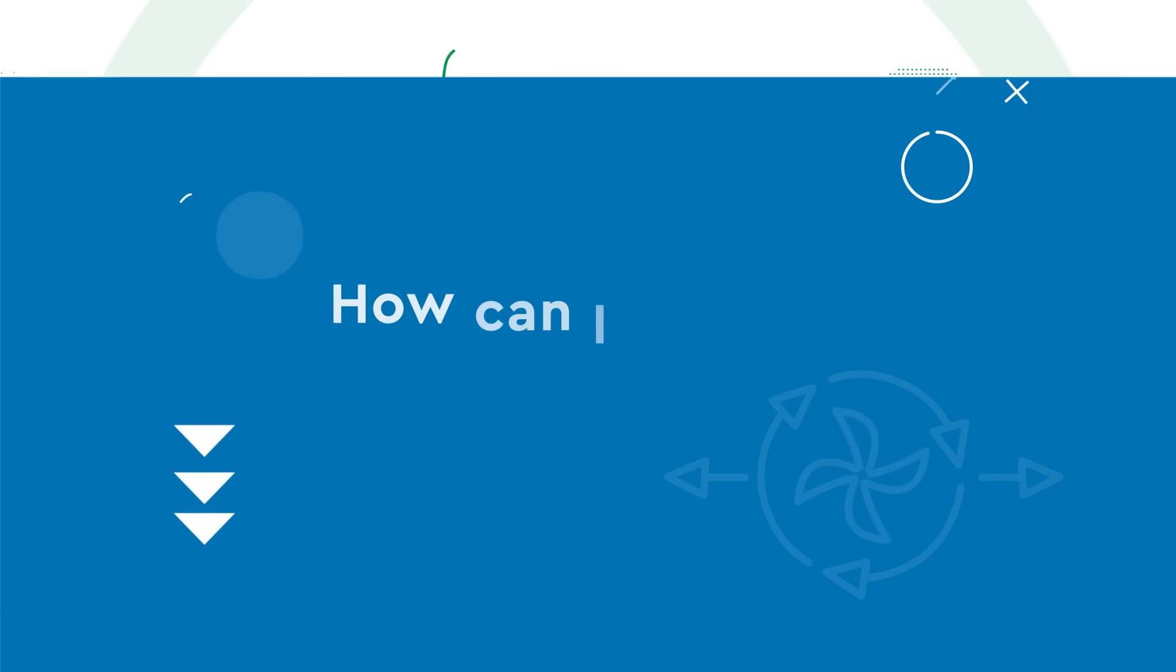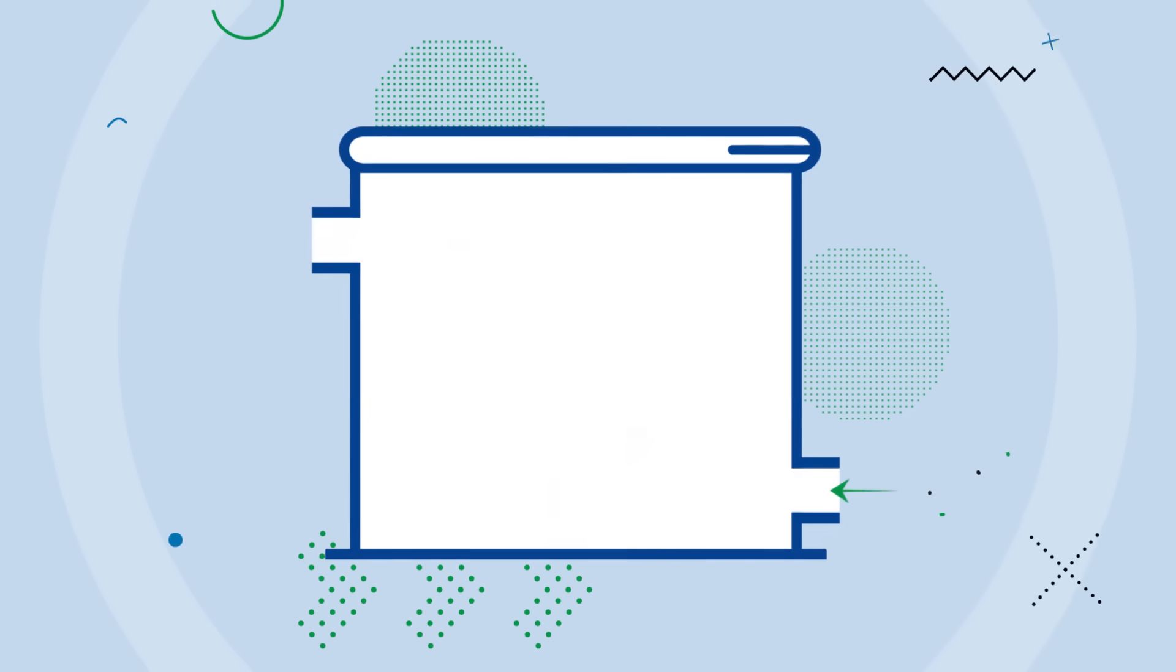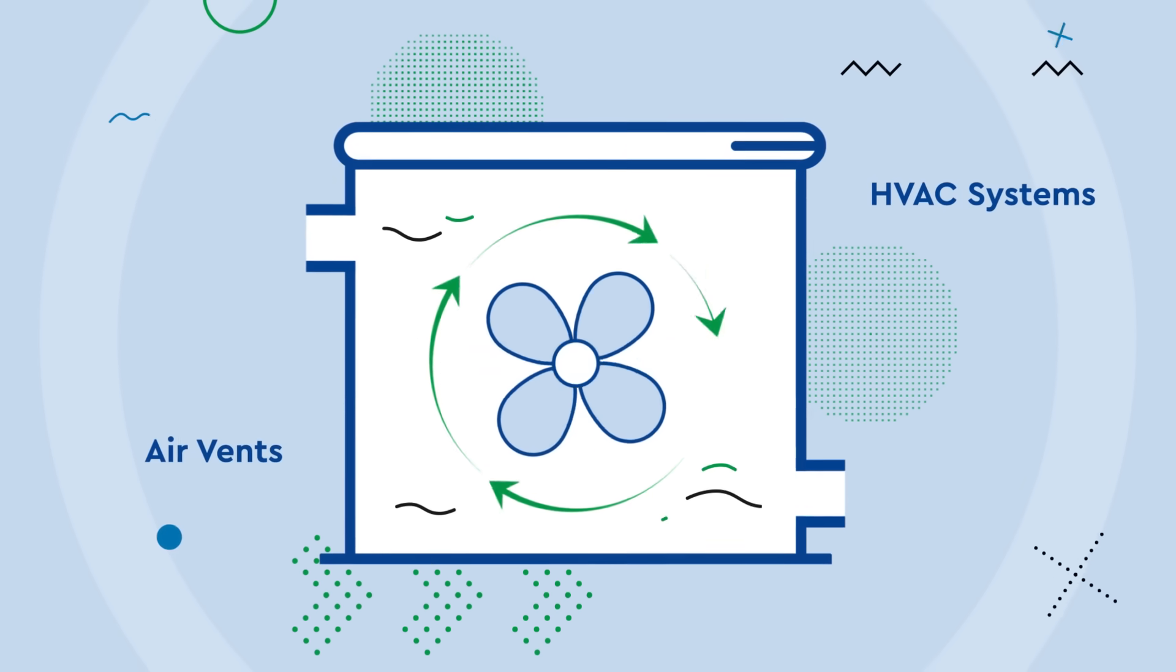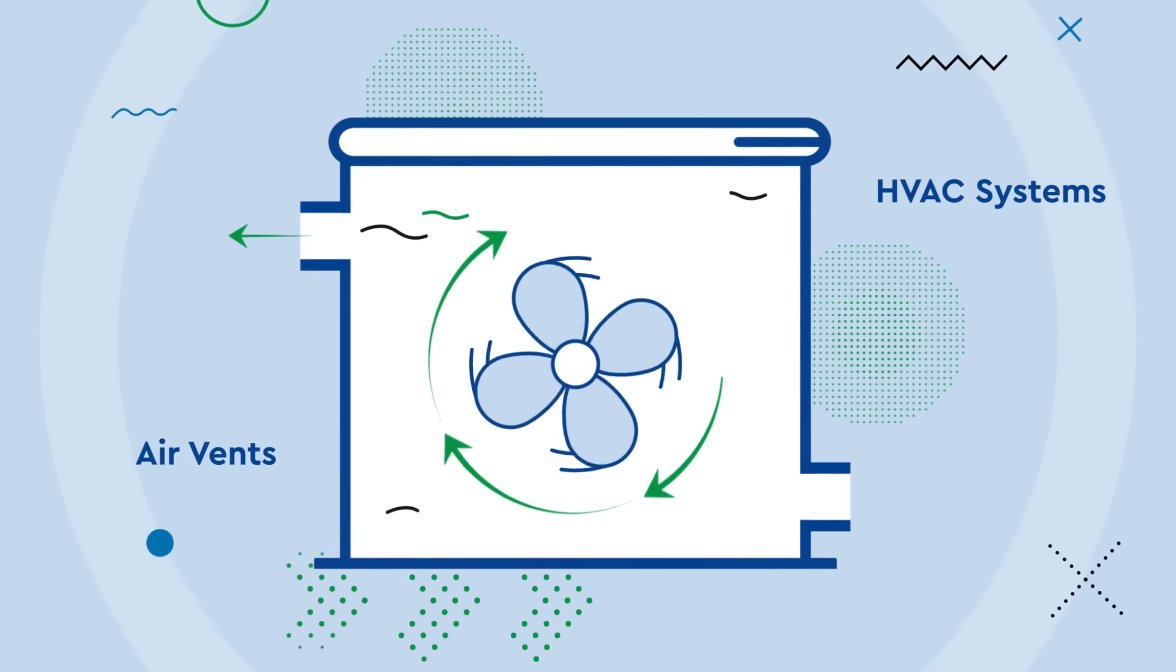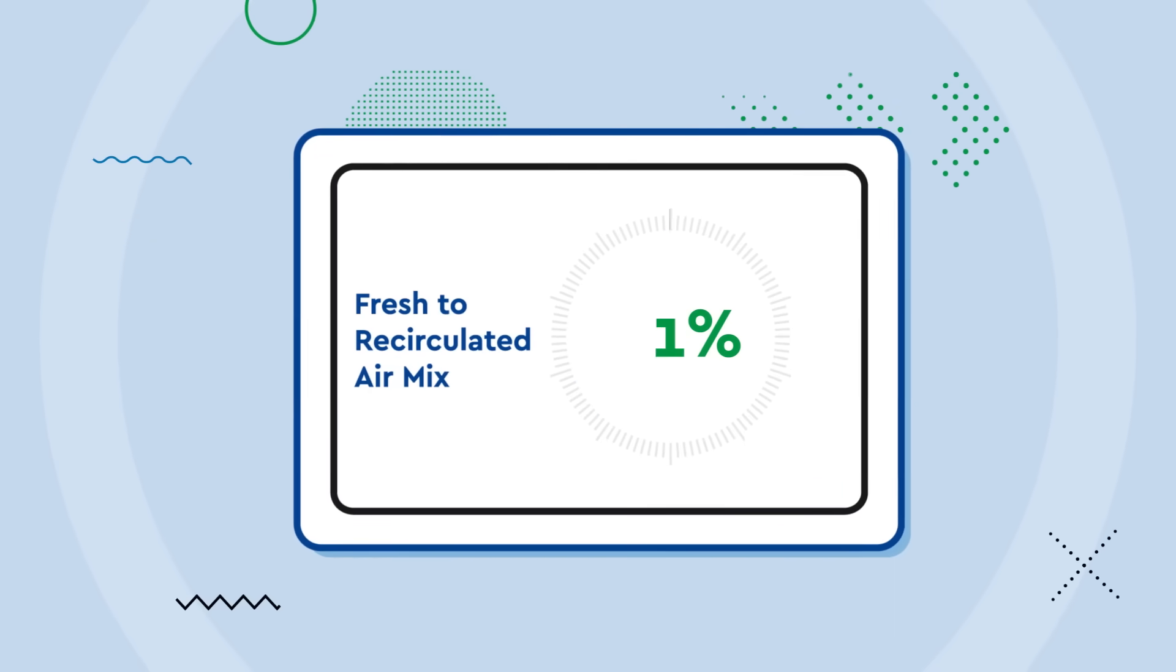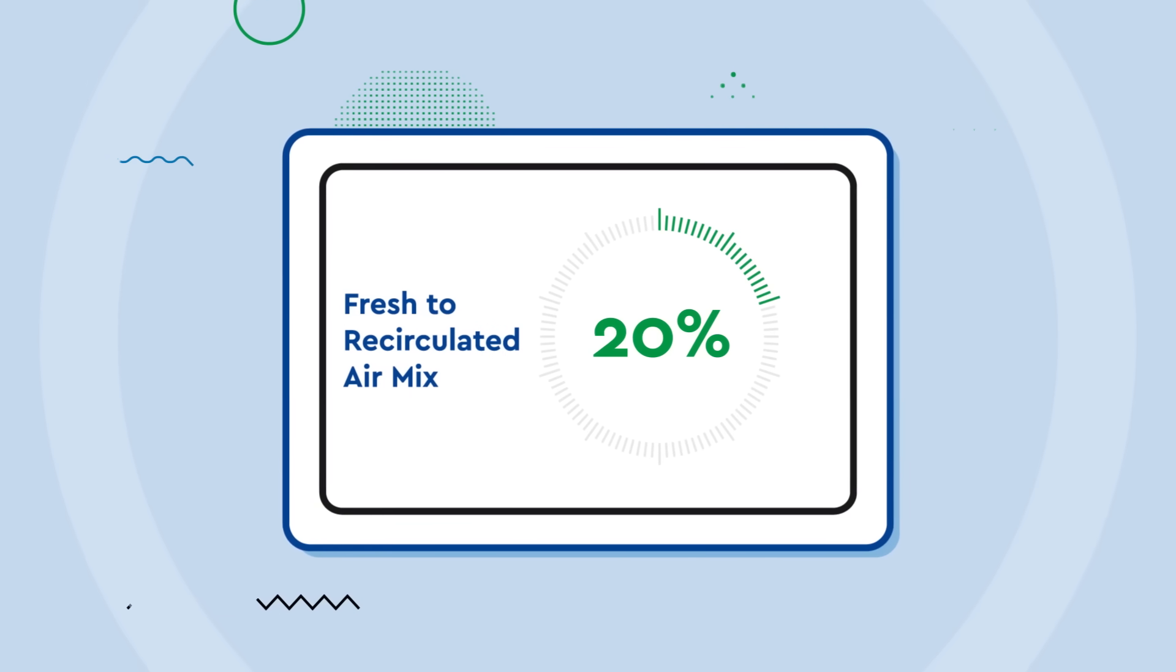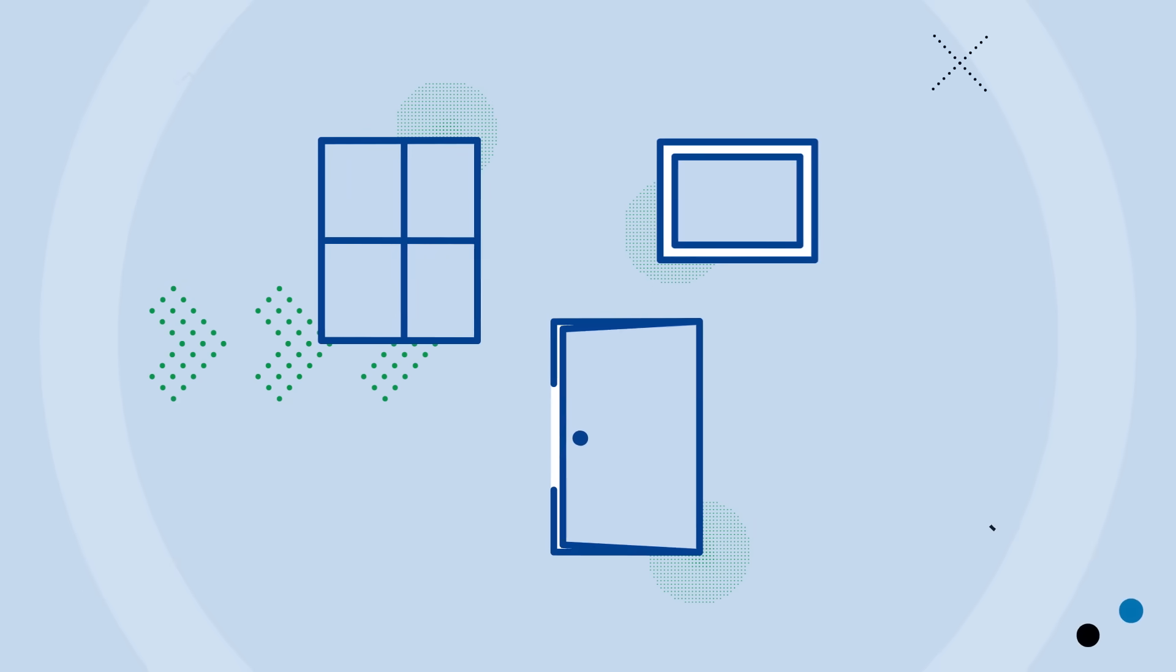How can I improve mechanical ventilation? Mechanical ventilation brings fresh air from outside into the building. These mechanical systems will provide adequate ventilation if they are set to maximize fresh air and minimize recirculation. You need to know how much fresh air it draws in and if this provides adequate ventilation. You may need to increase the rate or supplement with natural ventilation, opening doors, windows, and air vents where possible.